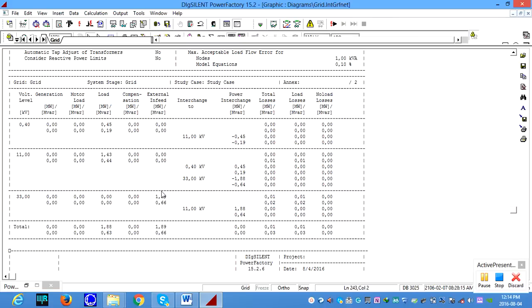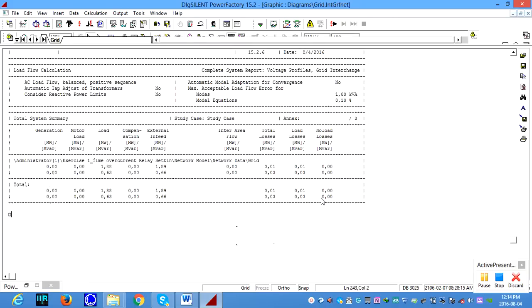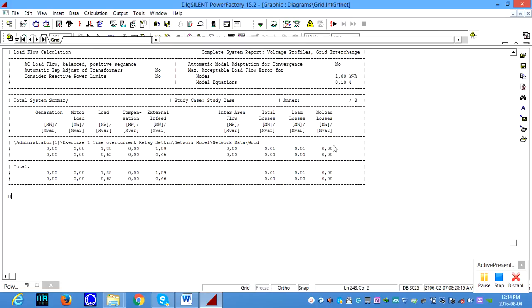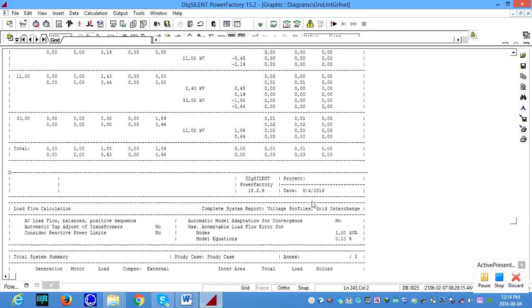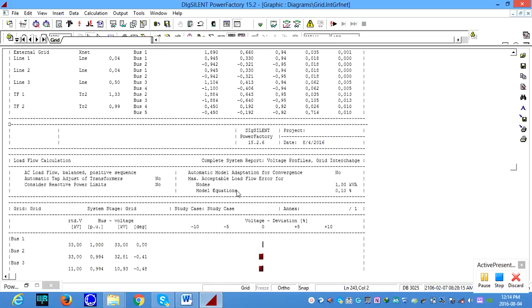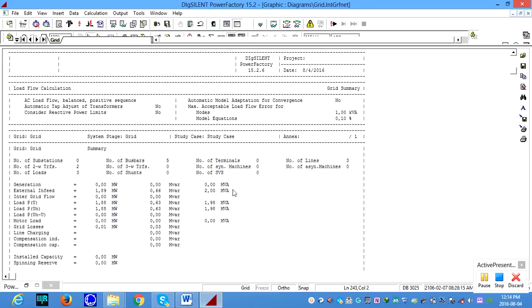and for 33 kV we have an infeed, that is, the external grid is feeding the network, and it is also giving the total losses, load and so on. And this is the total summary result if you look. Okay, so the system has an external infeed of 1.89 megawatt and 0.66 reactive power, and the losses are 0.01 megawatt and 0.03 megawatts. And this is the load losses. Okay, I think we are quite satisfied with the load flow results.